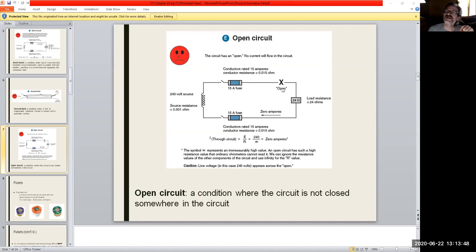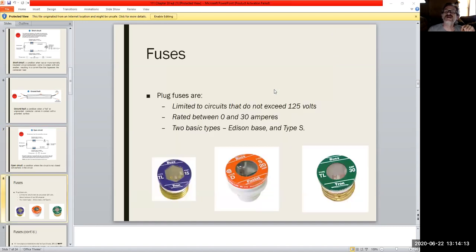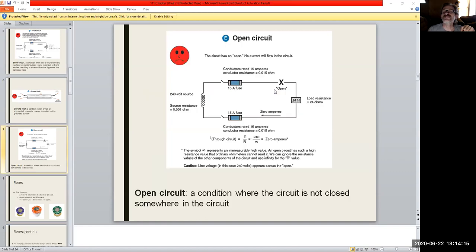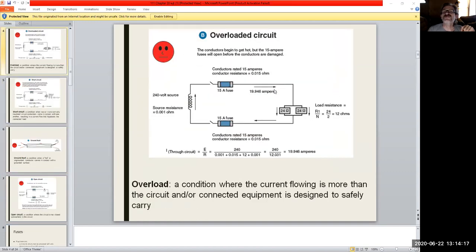There's different things that can happen. It's not always critter related. Who knows? Something happened. A ladder fell in the garage and hit a line, something goofy, but there's so many different scenarios, but you end up getting it open, and that's a pretty dead giveaway. No current whatsoever. You do have voltage at the source, then yeah, you get an open, broken line in there. So those are pretty much like your main scenarios that you'll ever run into, right?